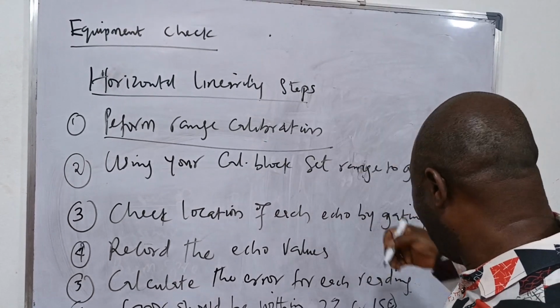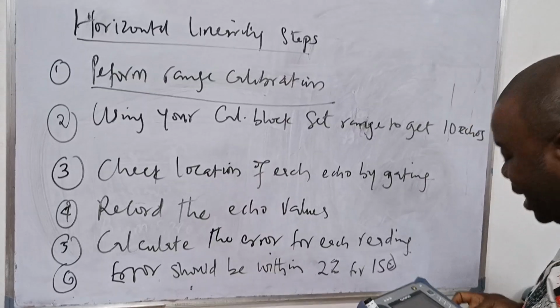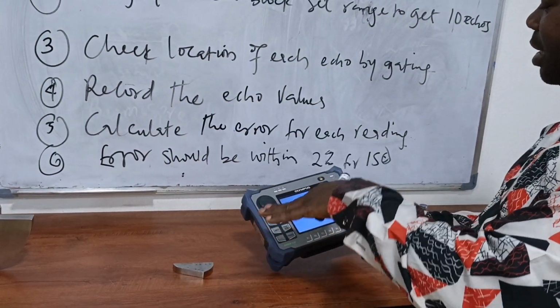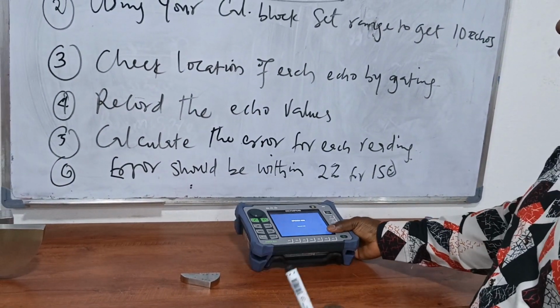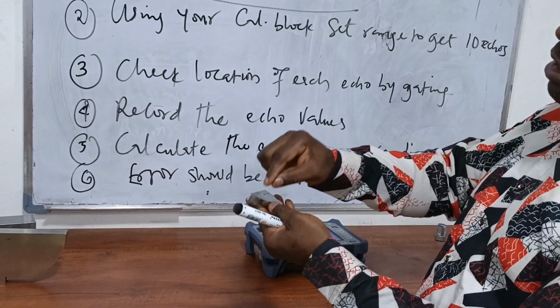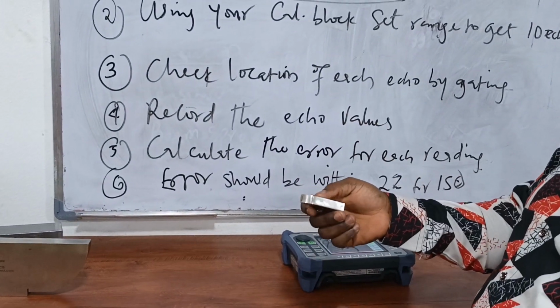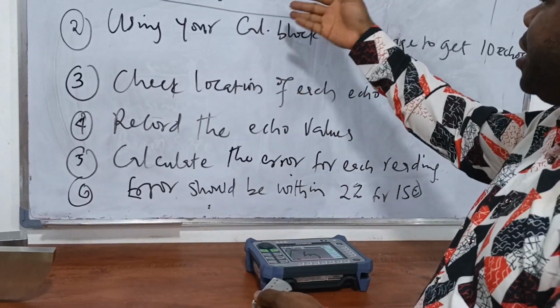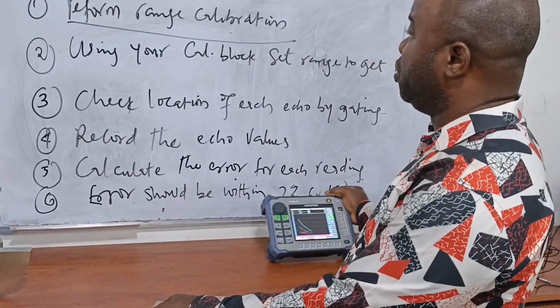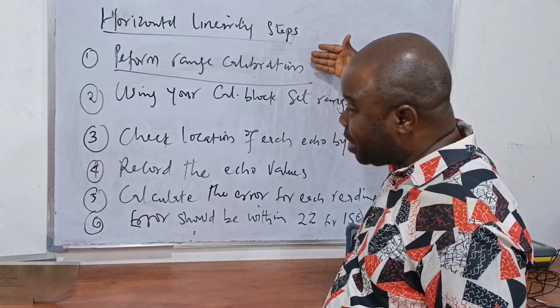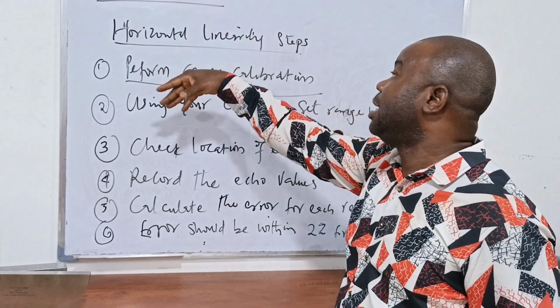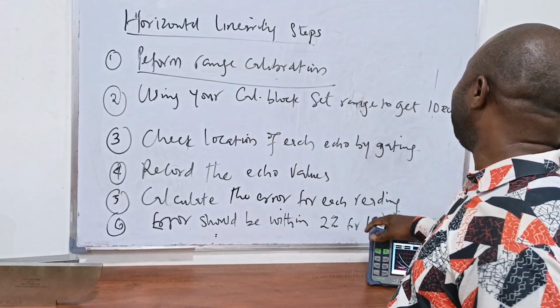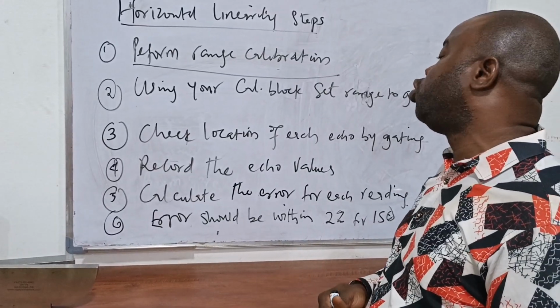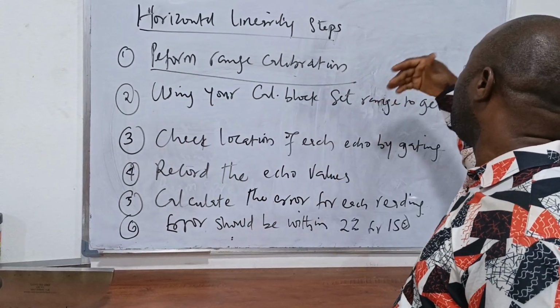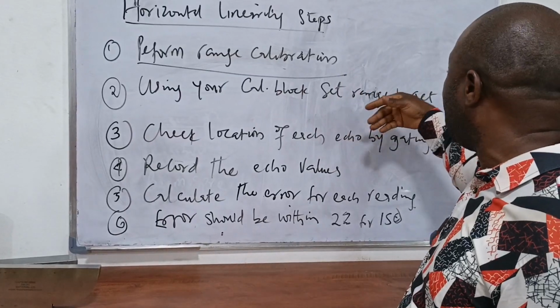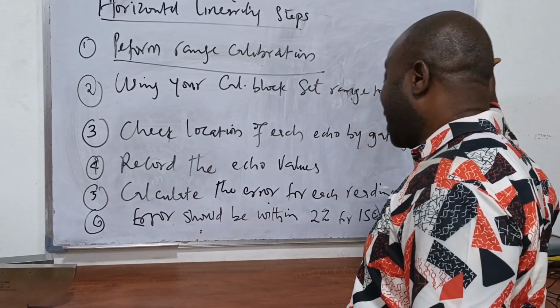It simply means you need to set up the equipment, do the necessary input, and ensure that the thickness values you are getting are accurate with respect to the range that you have set. So you must have calibrated your machine before you start doing the linearity check. Then the next thing you are going to do is use the calibration block. It depends on the calibration block you are using. Set the range for you to get 10 echoes.